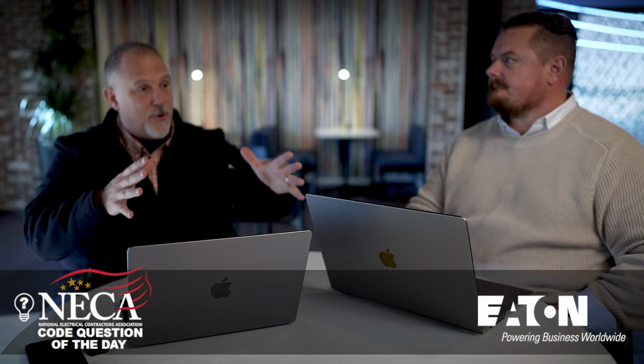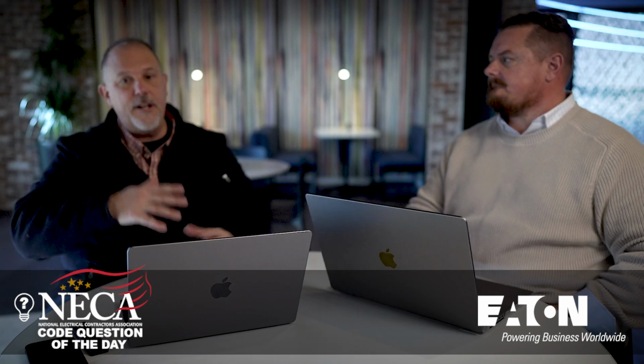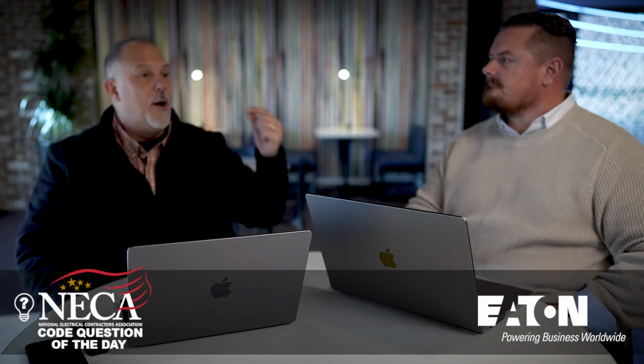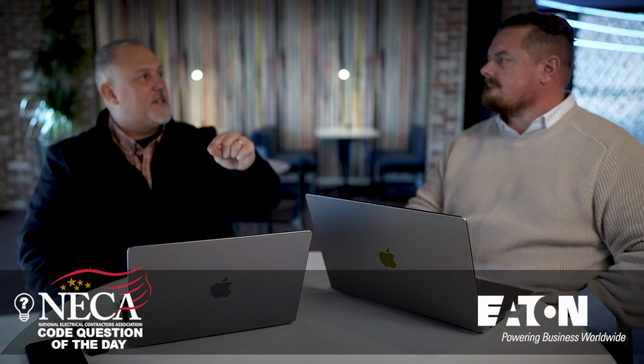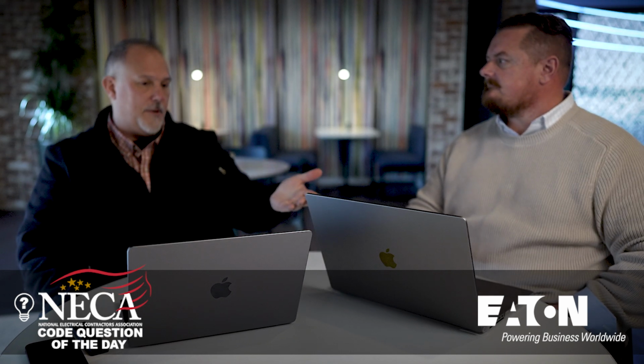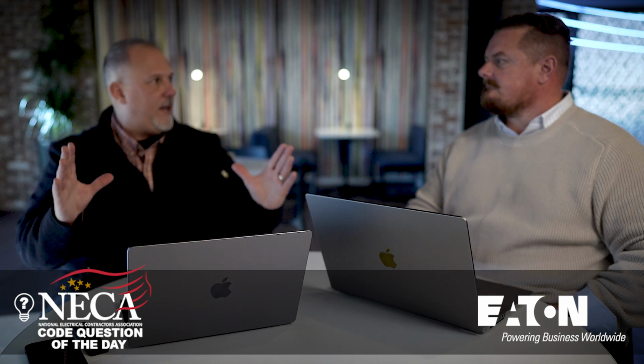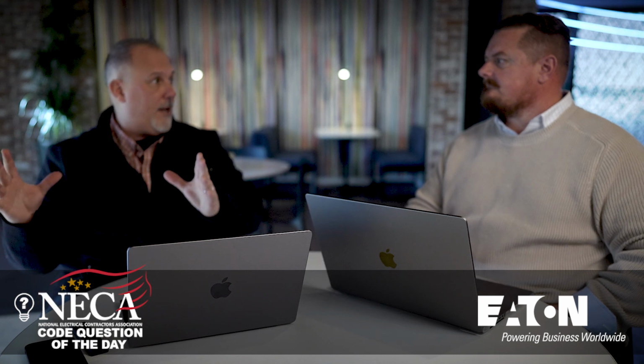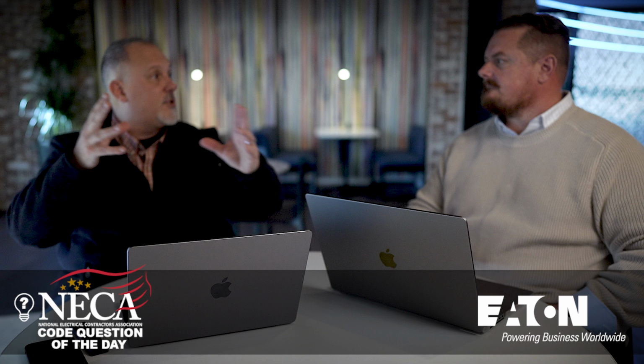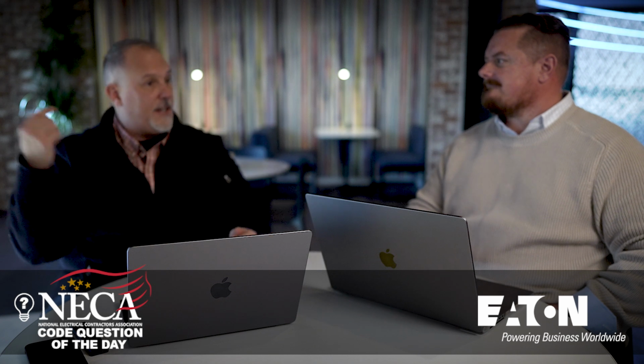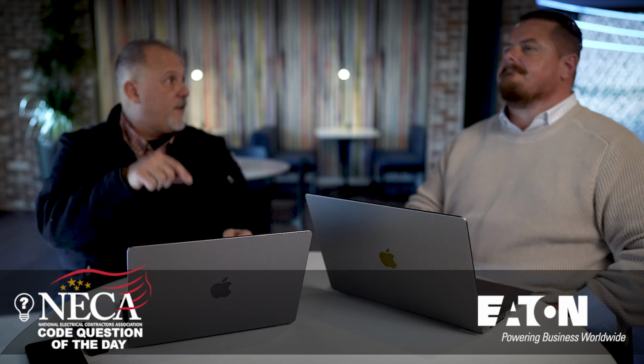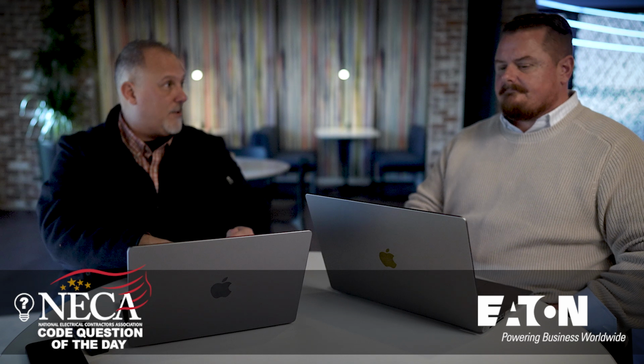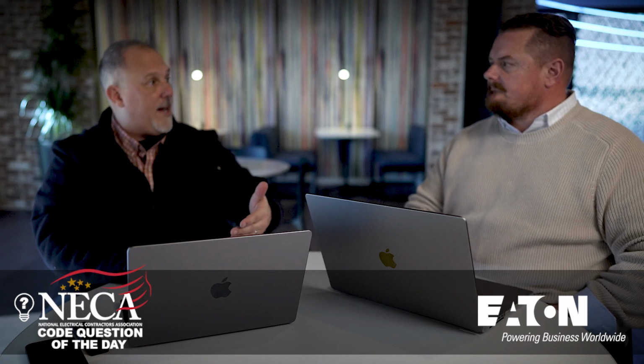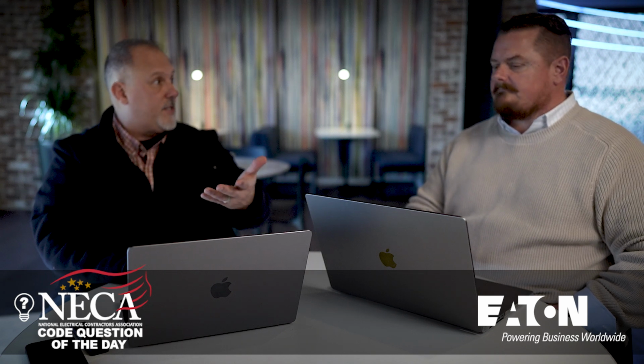I went right down the road of making the modifications in the field, because then you need a field evaluation, all that other good stuff. But what I learned was that specific manufacturer, and they probably others do it, said, we have a different panel. What we can do is ship the new panel. You take that one off, put this one on. They give you instructions, and then you get a field evaluation from a nationally recognized testing laboratory, and they were able to bring that HVAC unit right up to speed.